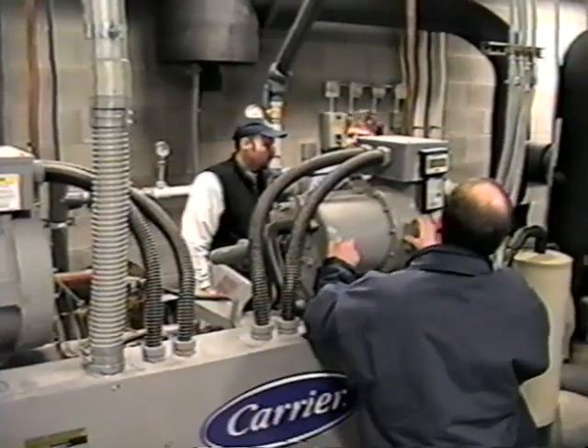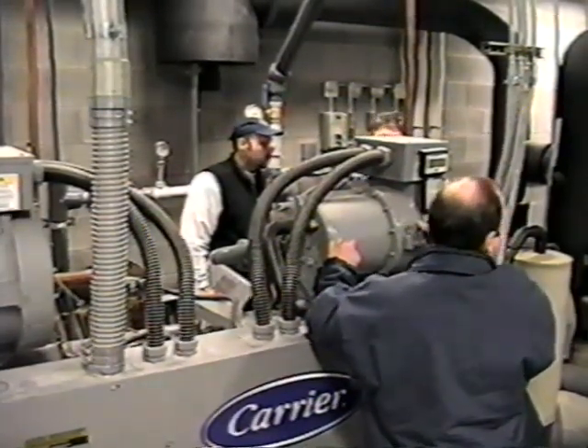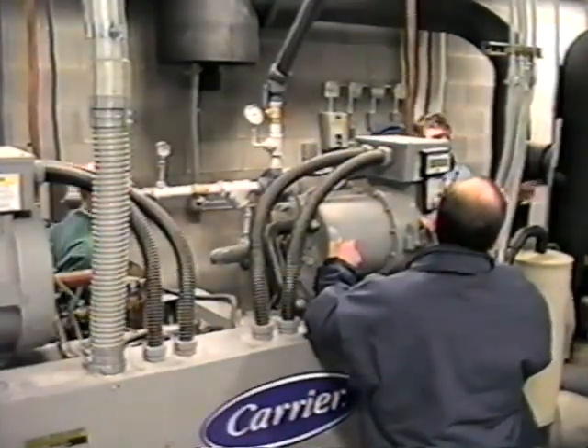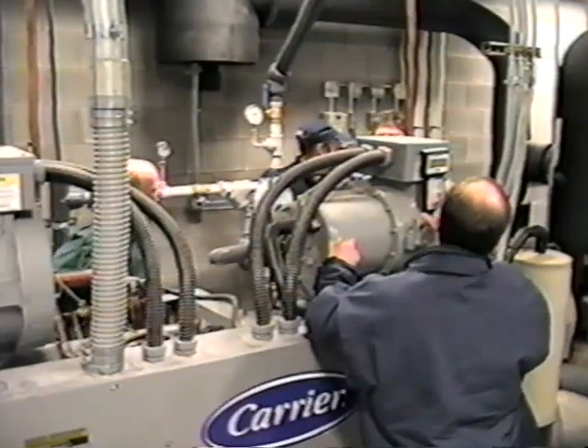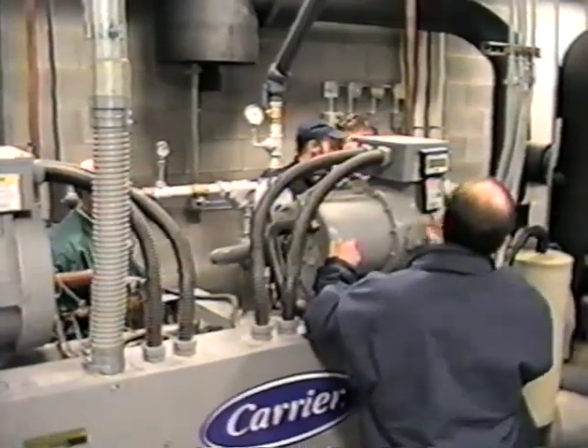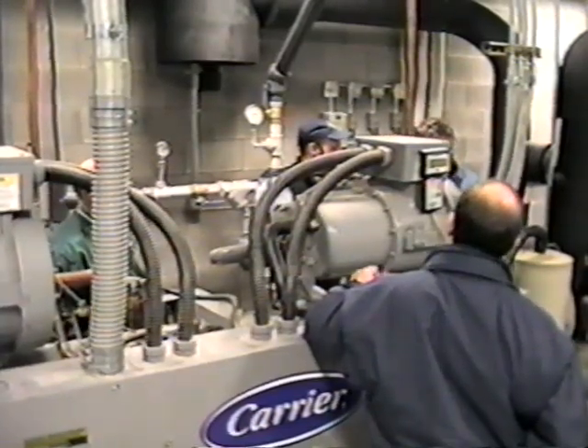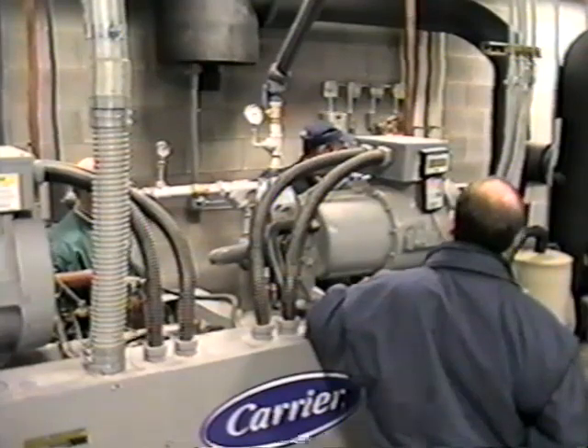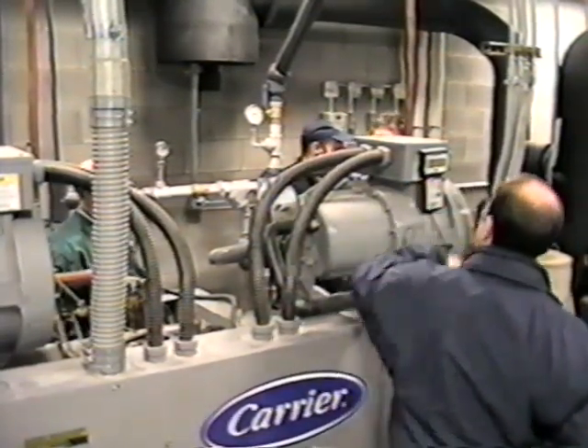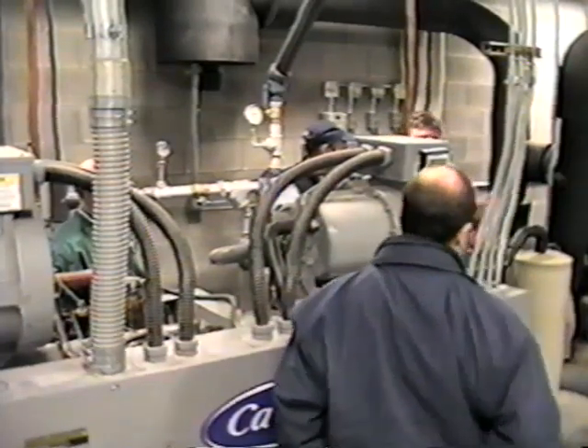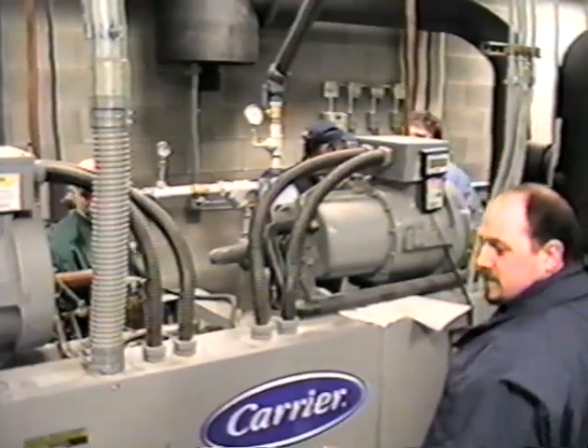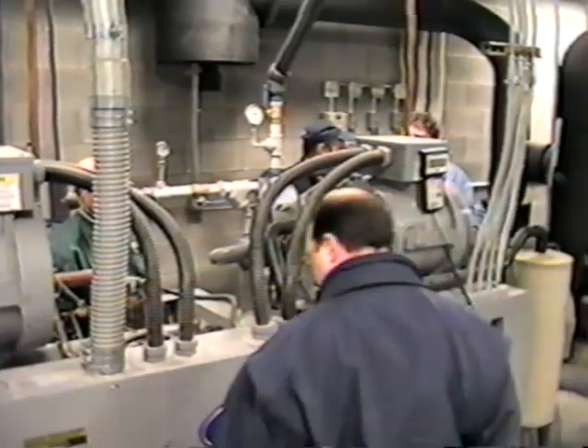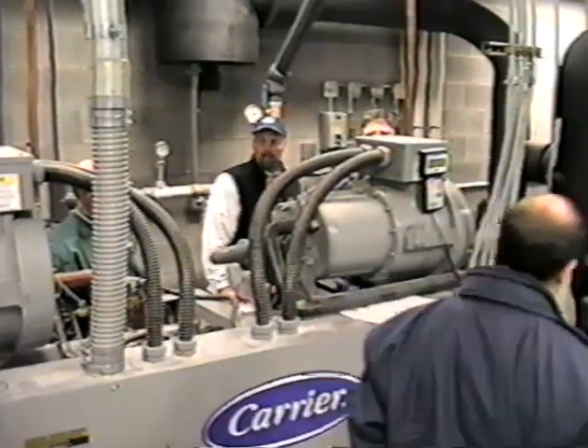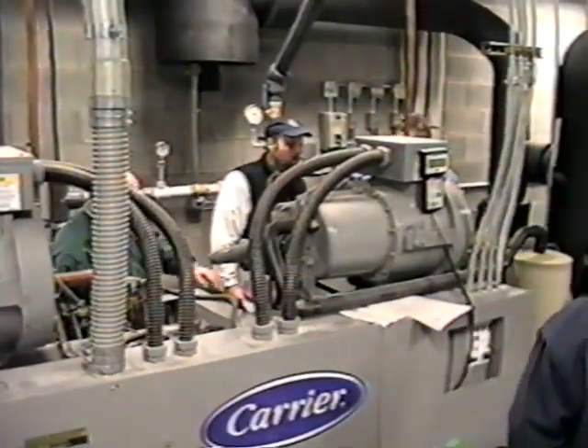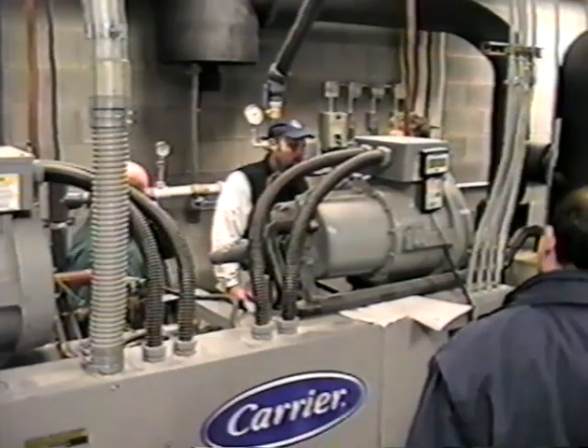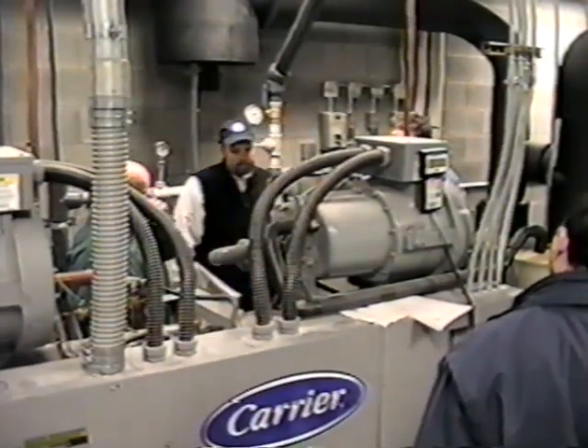How come this one used to be 10 pounds and now it's 2 pounds? Should we take care of these temperatures? I forgot the other day. Oh, well, yeah, this is for your condenser. It's critical that it doesn't get too low, or it'll trip out, and that's where we accidentally turned the valve there and tripped it out. For some of these we'll give you the tolerances you should be looking for, so yeah, we can give you plus or minuses on some of the stuff. Things are going to vary a little bit.